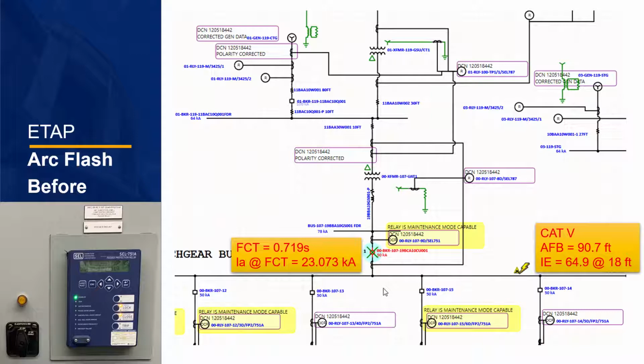The protective device settings are set in a way to maintain coordination with each other to ensure reliable operation. This is sometimes at the expense of increased incident energies. This is a scary realization, hence why arc flash mitigation programs are very important.